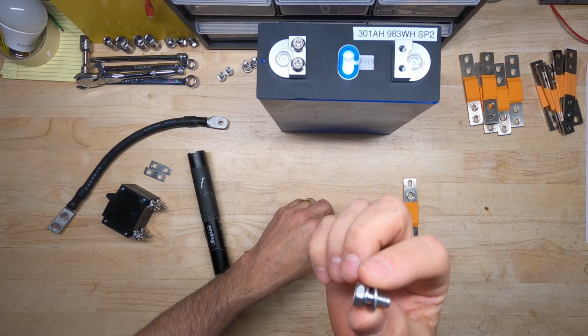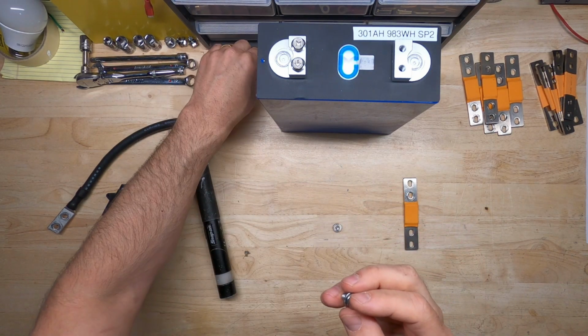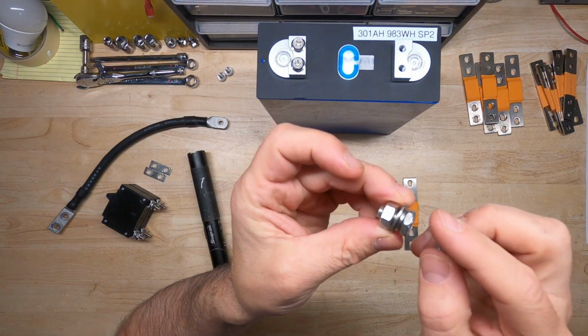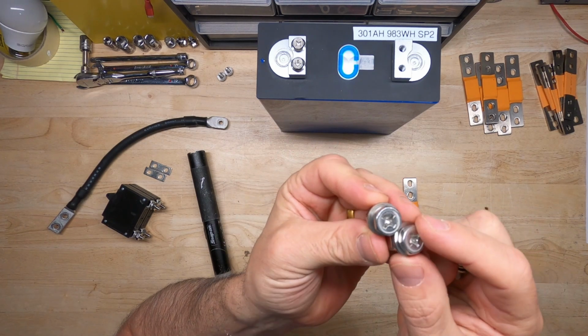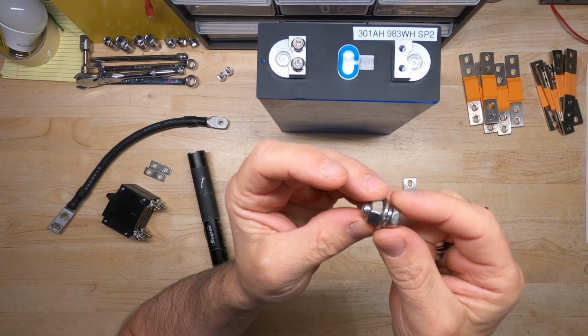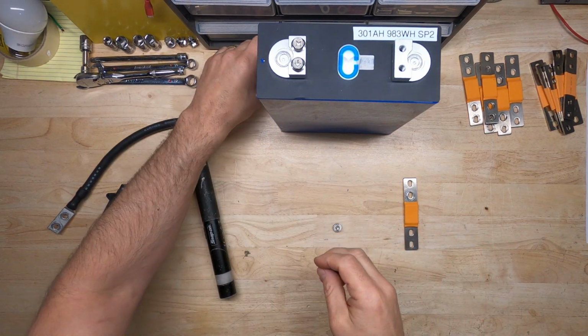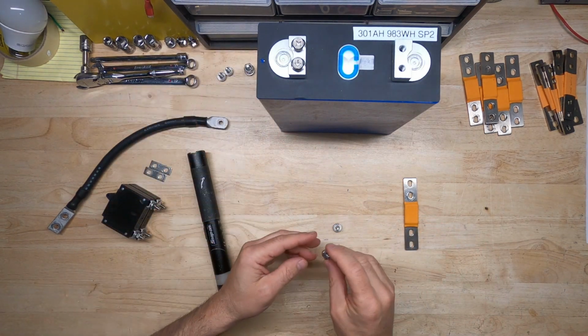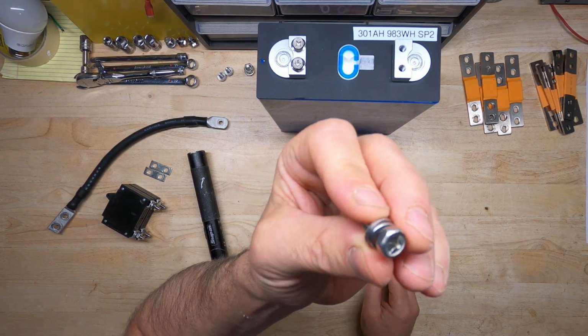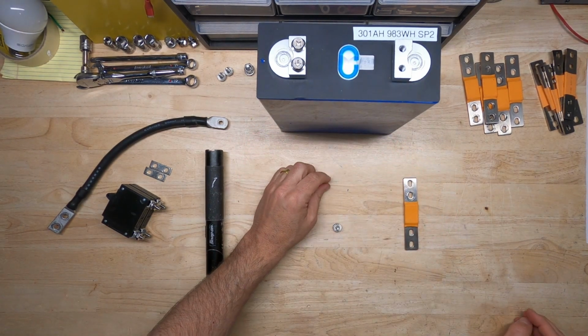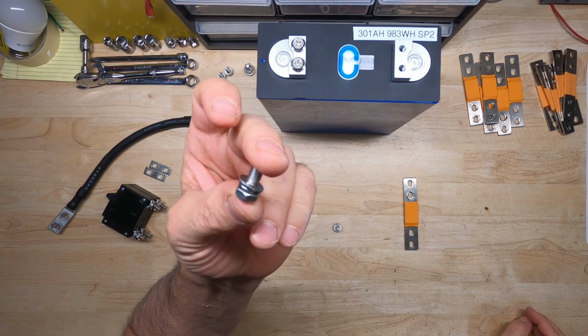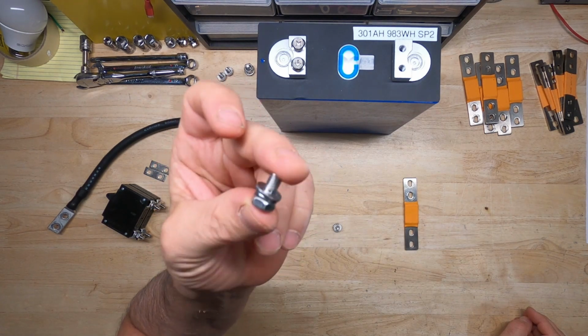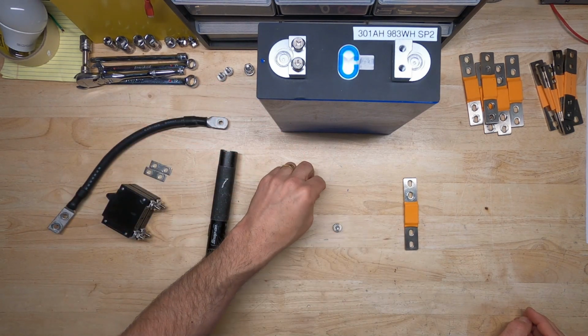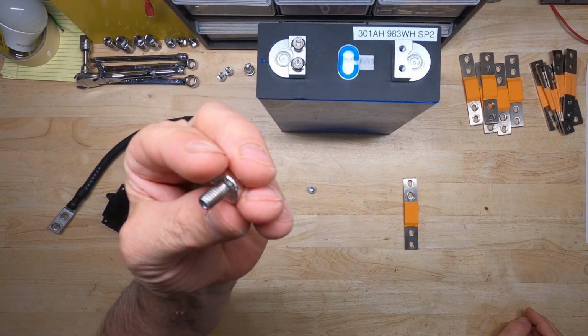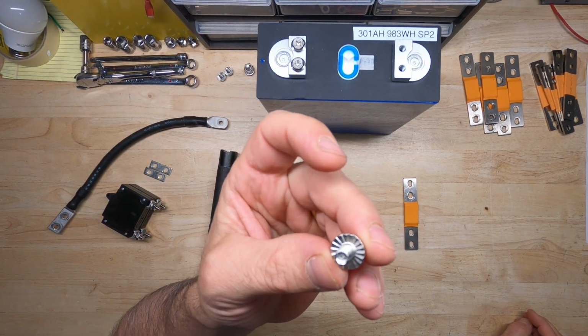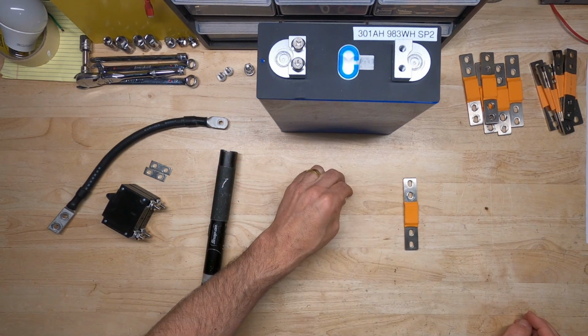So where else have we seen these style bolts? Well, we see these all the time on battery terminals. They use these even on the Yixiang box on the external battery terminals. These are the same thing, except they're M8. However, I think they use zinc bolts instead of whatever these mutant bolts are. So on these bolts we saw a minimum of 150 to 200 max, so that's definitely a fail. On the standard serrated bolts we saw an average temperature of around 100 degrees, definitely a pass.